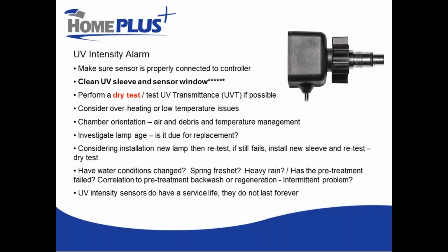Extreme cold can also be an issue. So in the winter, if you're running really low ambient temperatures and suddenly you're getting more and more intensity alarms, you probably need to warm up the air temperature in your treatment room so that your system can run at the ideal operating temperature.